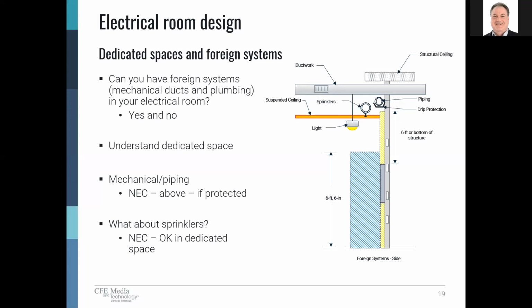Typically, it's not good practice to put piping above that 6 foot above a gear, if you're able to have that much space in an electrical room. But you should have some sort of drip pan or protection. You really shouldn't locate it there in general. Above the dedicated space, you can have it in the room. The sprinklers are allowed in the dedicated space. Those are critical to the room. However, again, good practice would be to locate the sprinklers just outside of this dedicated space over the top of equipment.